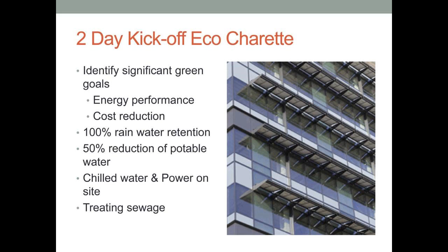Beyond energy performance and a reduced cost for the mechanical system, the design team identified a desire to obtain 100% capture and reuse of rainwater on site, have a minimum of 50% reduction in potable water use, and also sought to provide substantial amounts of power and chilled water on site from a combined heating, cooling, and power plant. All sewage was also to be treated on site and reused for non-potable uses. Overall, the design team was quite successful at addressing these issues and focusing on these challenges. The building obtained a LEED Platinum rating and is often viewed as one of the most complex buildings in the country to achieve such a high standing.